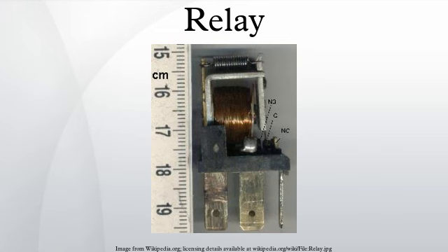Relay application considerations. Selection of an appropriate relay for a particular application requires evaluation of many different factors. Number and type of contacts: normally open, normally closed, contact sequence make before break, or break before make. For example, the old-style telephone exchanges required make before break so that the connection didn't get dropped while dialing the number. Rating of contacts: small relays switch a few amperes, large contactors are rated for up to 3000 amperes, alternating or direct current.